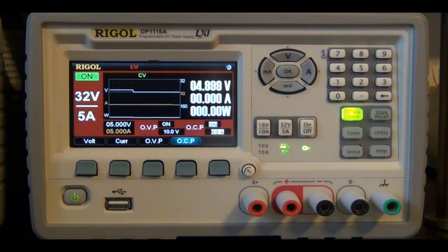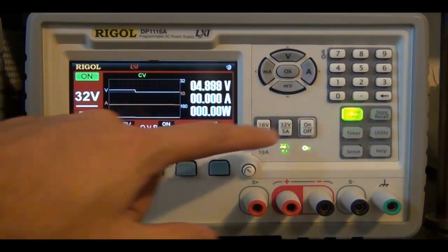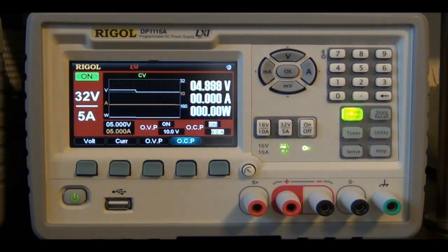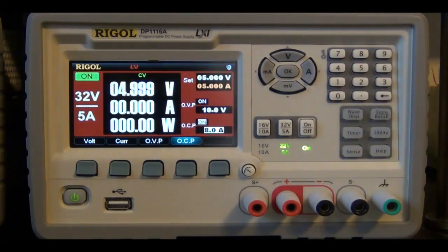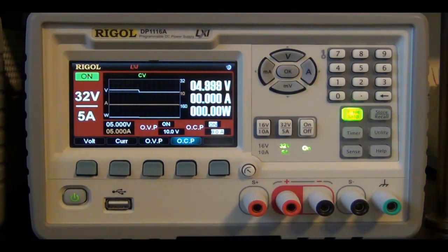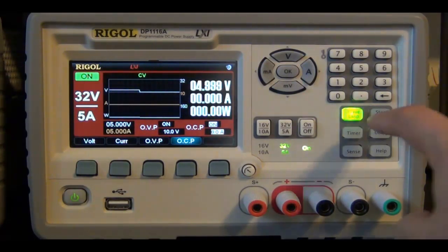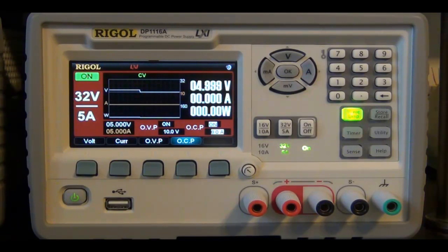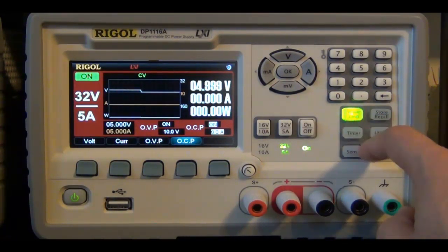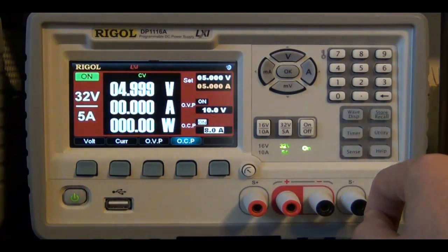So if you're testing something and you would like to monitor how the current changed with time, or how much power consumption changed with time, you can press that and it will plot it for you. Or one thing I found that could be quite useful is that, let's say you've been running it and you detect a fault in your system that caused a current spike, even if you were not in this display, you can still click this and it's been sampling in the background even when it's not active. So you come back and you click that and you can see immediately if there was a spike somewhere, and you can find out. So it's a very useful fact that this is always running in the background. So let me disable that so we can go back.